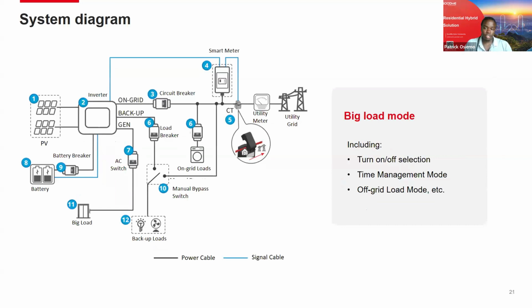The same generator port can be configured to become an output as well. So the generator port is being configured to handle big loads. Big loads are the loads that draw too much power when starting up, or that just consume a high amount of power. With these big loads connected to that port, once you've reconfigured the generator port to become an output, those big loads can be turned on and off depending on various conditions. You can put time management on that. You can put it on as off-grid. You can set the loads to switch off in certain conditions. So they are very flexible in how you power loads connected on the generator port.